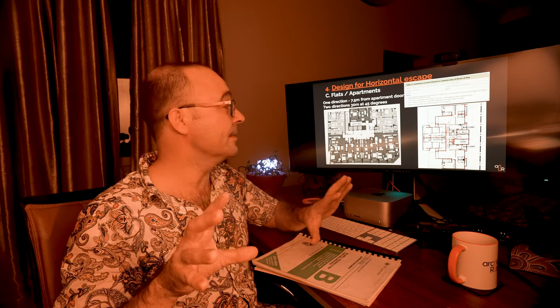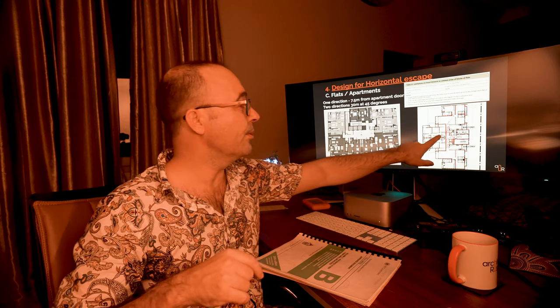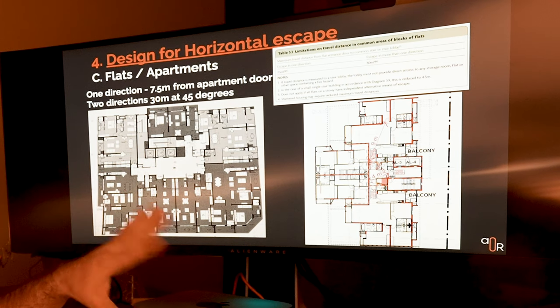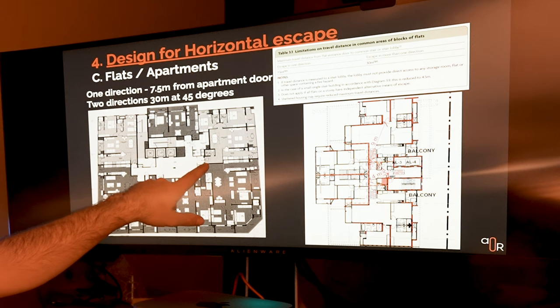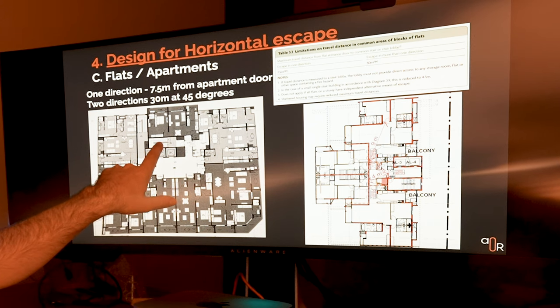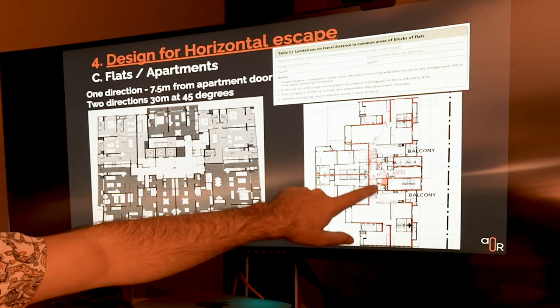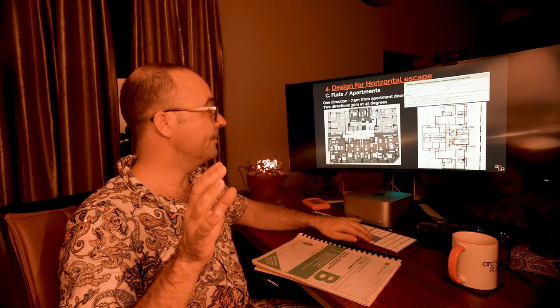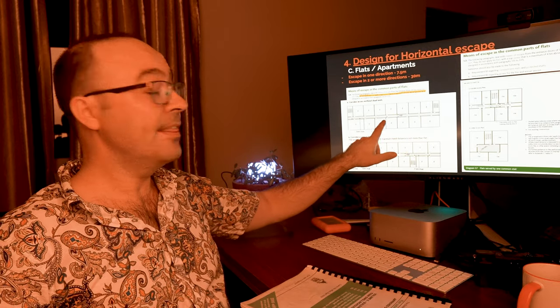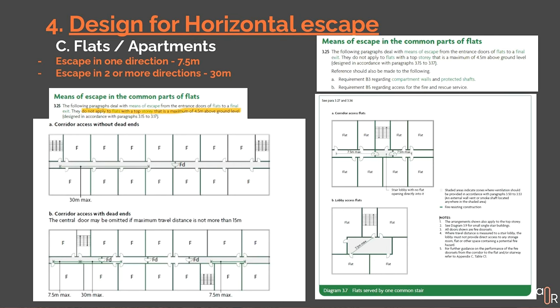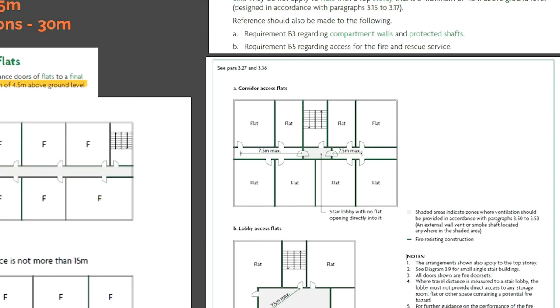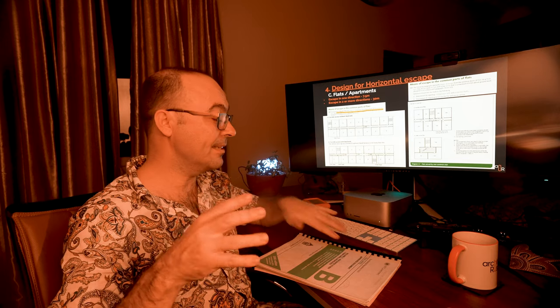For flats and apartments, from the actual apartment door to the fire escape it should be no more than 7.5 meters. So if you've got the front of an apartment here, it's no more than 7.5 meters to that escape stair. Now if you've got two directions — more than one fire escape in the apartment building — you can put them on either side and that can go up to 30 meters. So for apartment buildings, you can go up to 30 meters if you've got a point of choice. With one stair it's only 7.5 meters.